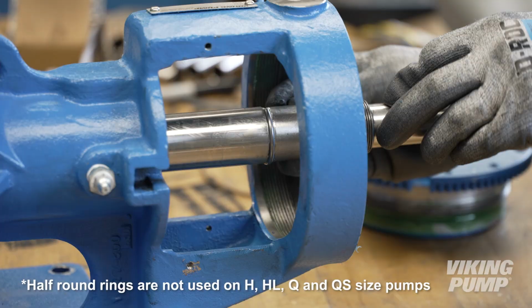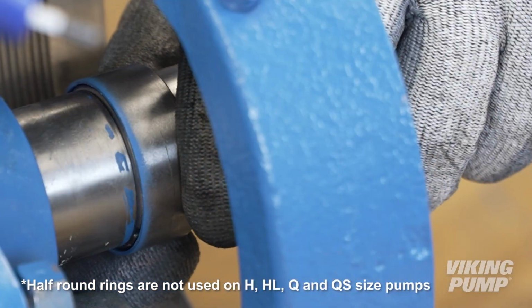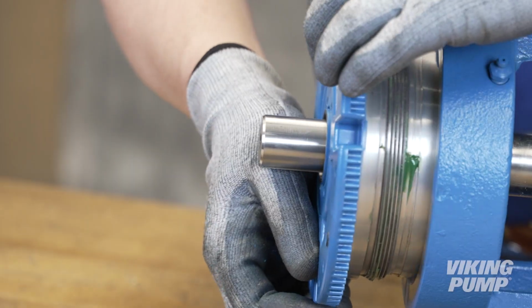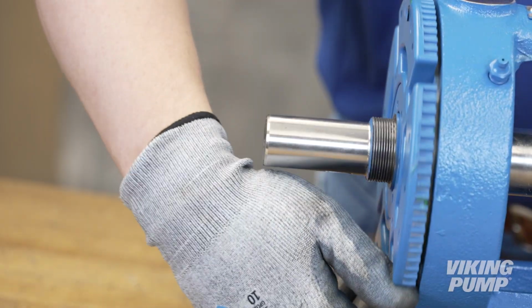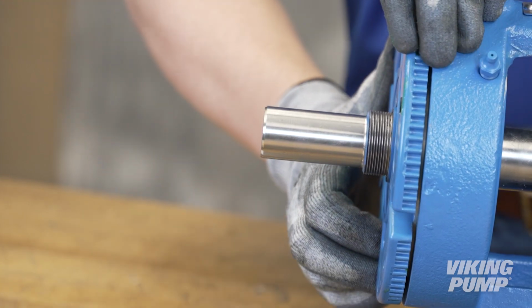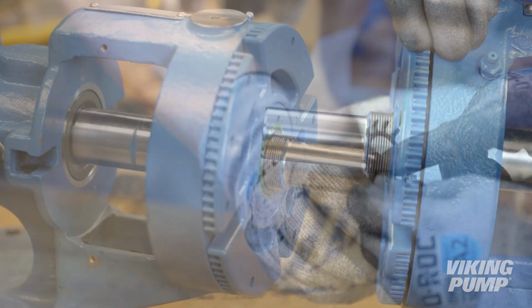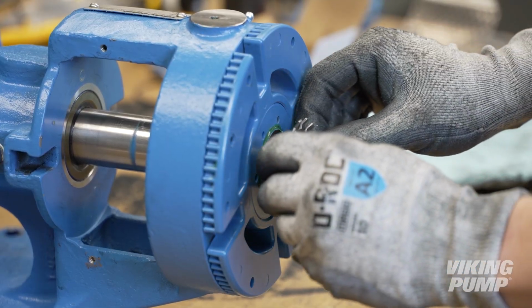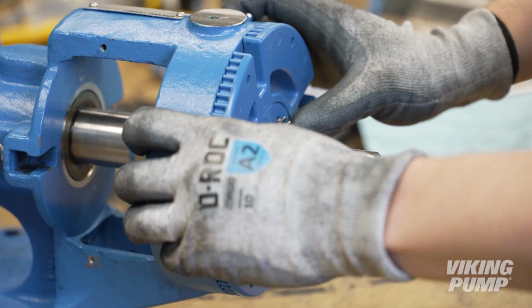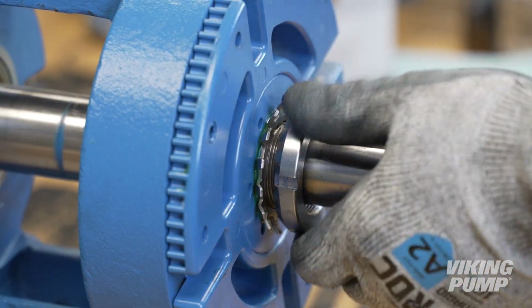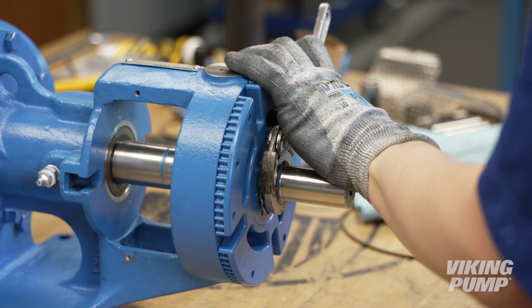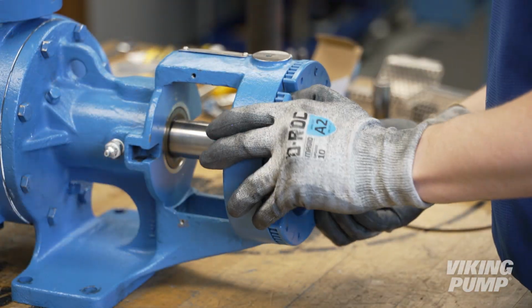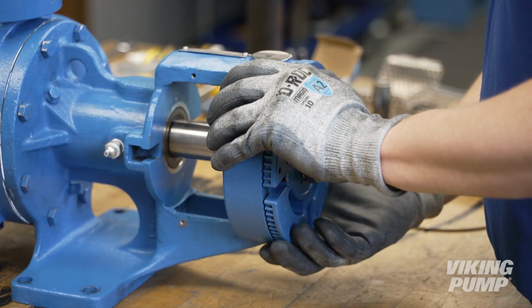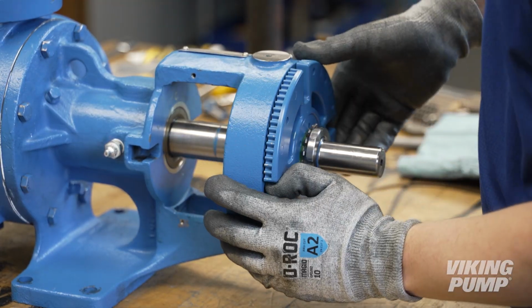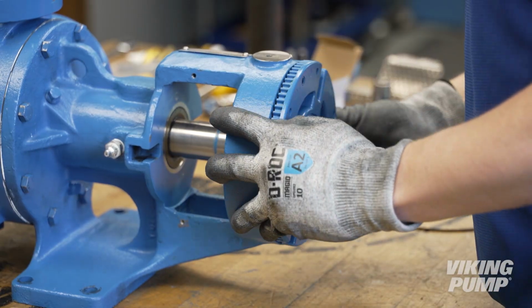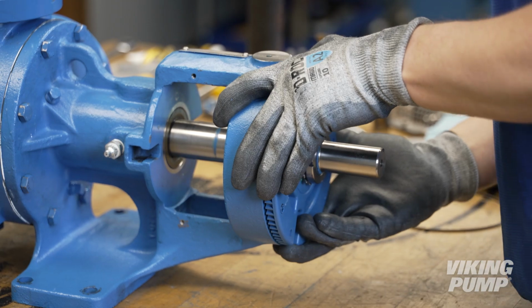Install the half-round rings. Install the bearing spacer collar over the half-round rings. Since the seal is engaged in pushing the rotor shaft out of the pump, the bearing housing will need to be installed to aid with head installation. Install the lock washer by aligning the tab through the slot on the shaft. Install the lock nut. Fully tighten the lock nut. Loosen the bearing housing to open the clearance and pull the rotor into the casing. Use care when turning the bearing housing. Stop if you encounter resistance. Turning too far may overcompress and damage the seal.